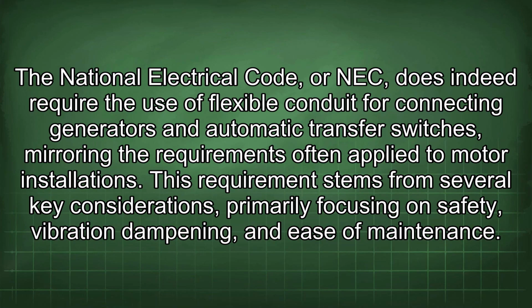The National Electrical Code, or NEC, does indeed require the use of flexible conduit for connecting generators and automatic transfer switches, mirroring the requirements often applied to motor installations. This requirement stems from several key considerations, primarily focusing on safety, vibration dampening, and ease of maintenance.